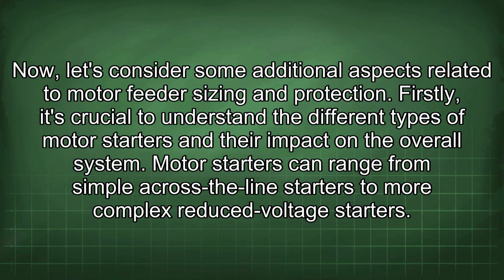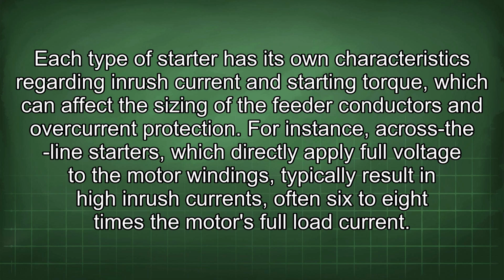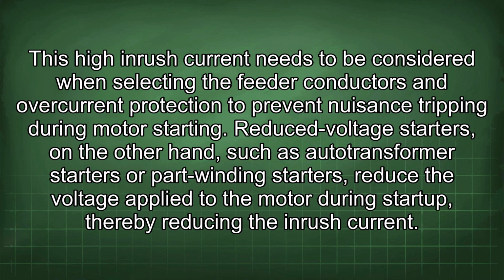Motor starters can range from simple across-the-line starters to more complex reduced-voltage starters. Each type of starter has its own characteristics regarding inrush current and starting torque, which can affect the sizing of the feeder conductors and overcurrent protection. For instance, across-the-line starters, which directly apply full voltage to the motor windings, typically result in high inrush currents, often 6 to 8 times the motor's full load current.